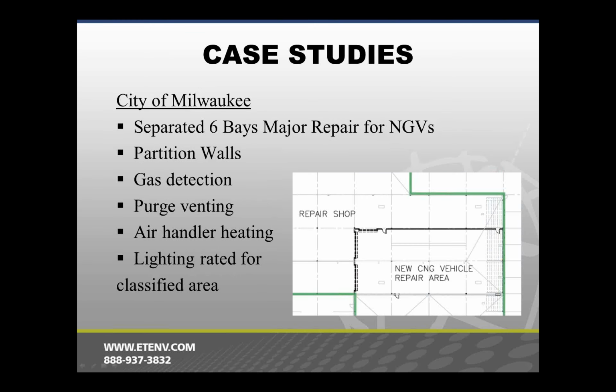And this one, to my knowledge, has not been built yet, but it's been designed. It's a City of Milwaukee repair shop, and their approach was to separate an area of a larger building that could accommodate up to 6 vehicle repair spots for major repair of NGVs. They separated it with partition walls and ended up, again, with all the bells and whistles, gas detection, purge venting. They used an air handler system for heating, and one thing that's a little bit unique about this one is the lighting was actually up tight to the ceiling and also rated for the hazardous environment.